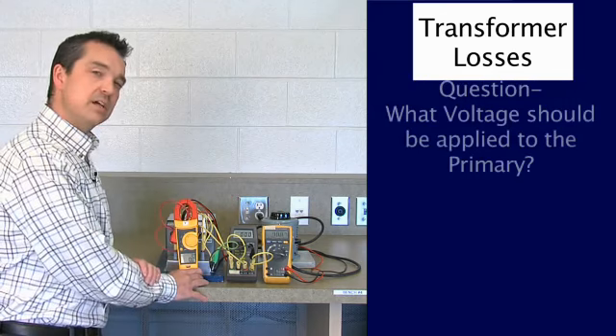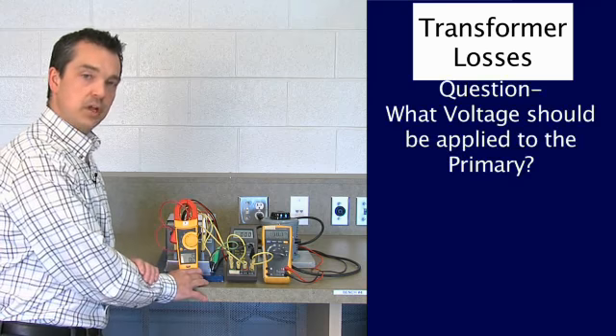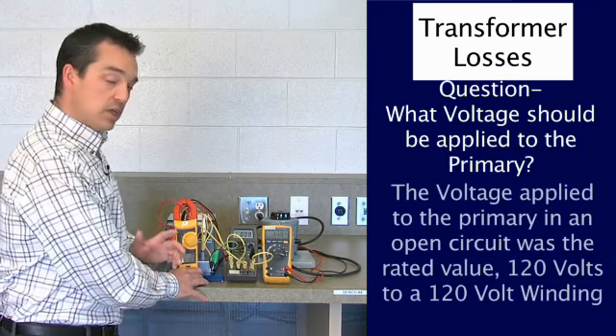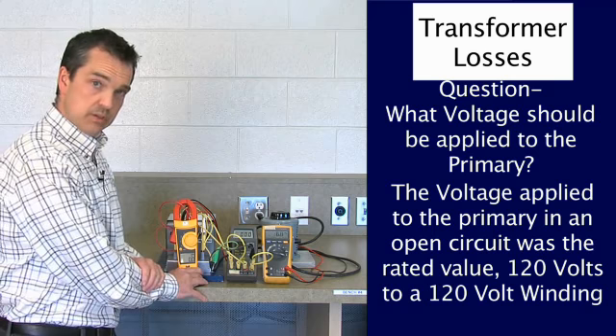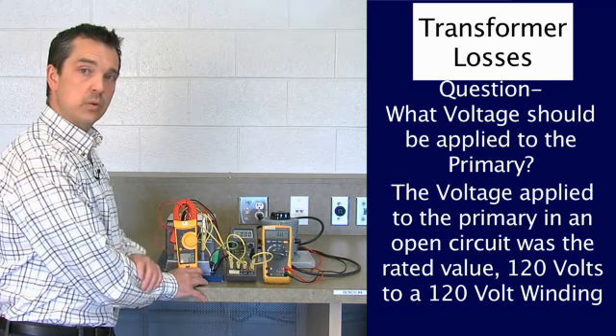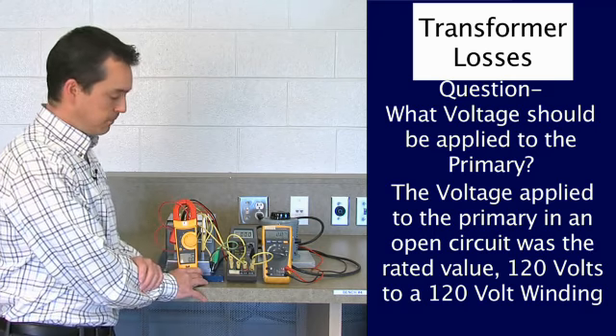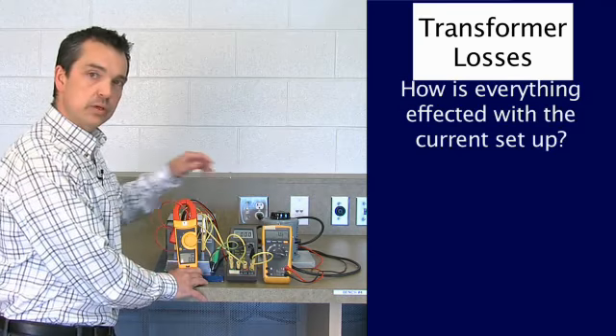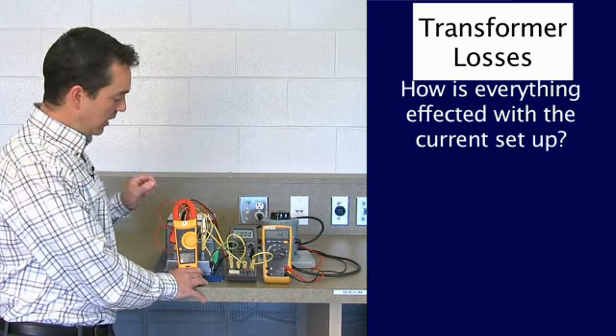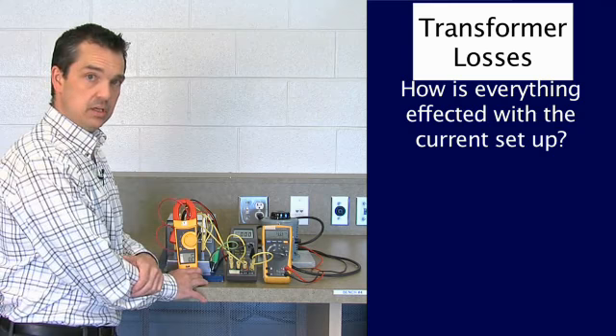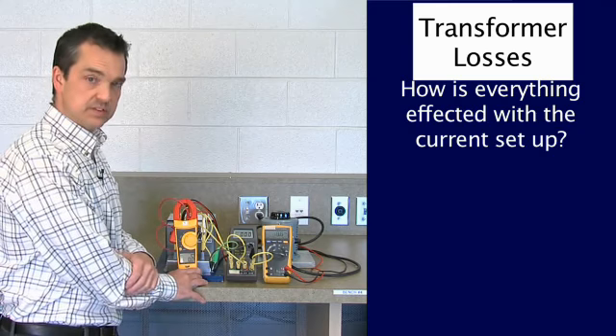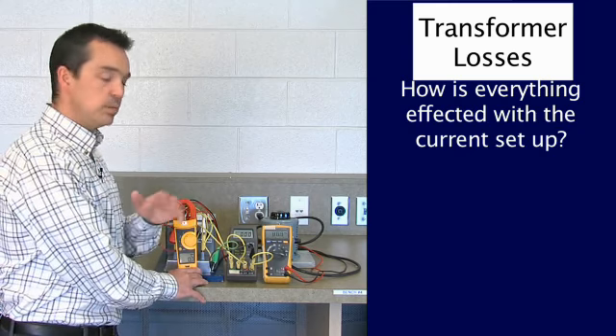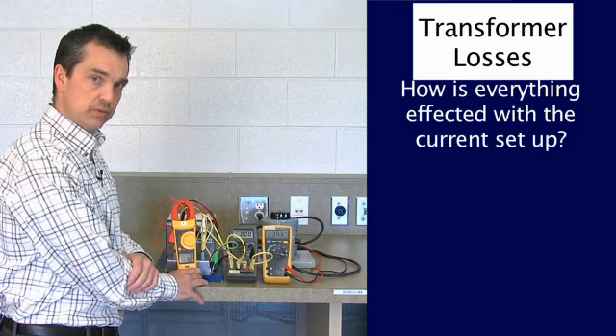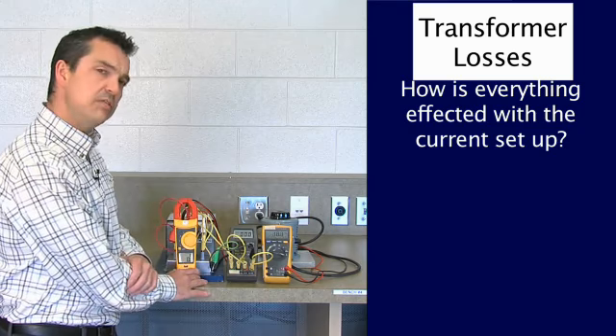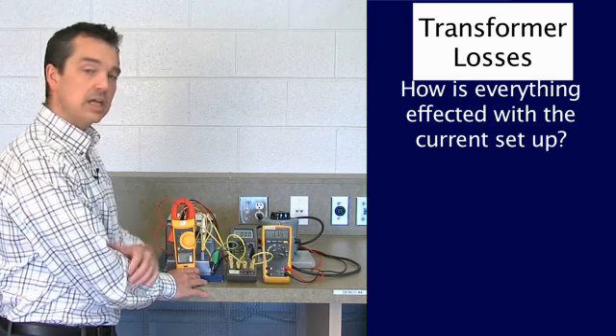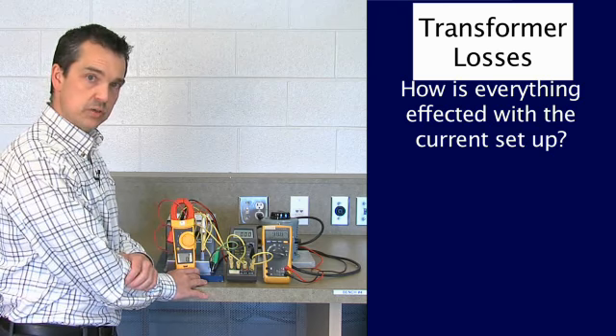The question is going to be asked here though, what voltage should I apply to the primary? And the voltage I applied to the primary in an open circuit was the rated value, 120 volts to 120 volt winding. If I apply 120 volts to this now, I have a short circuit on my secondary. I will have 240 volts induced into the secondary. It will simply be a short circuit. All I'm going to do is blow the fuses. So it's going to be a very small value of voltage, and you'll see that when I turn it on and I apply the voltage to it.